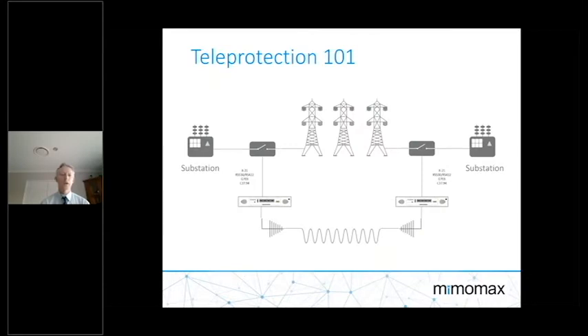So here's an image of what a typical transfer trip type relay system might look like. What we're seeing here is a relay at both ends of a transmission line. The idea is that we're protecting the transmission infrastructure, using communications devices to monitor both ends of the network and apply those relay signals, switching those relays really quickly.